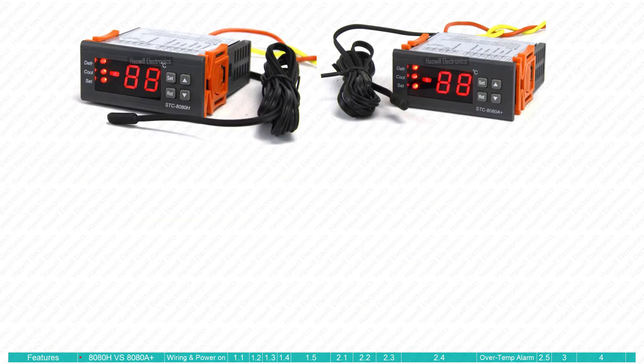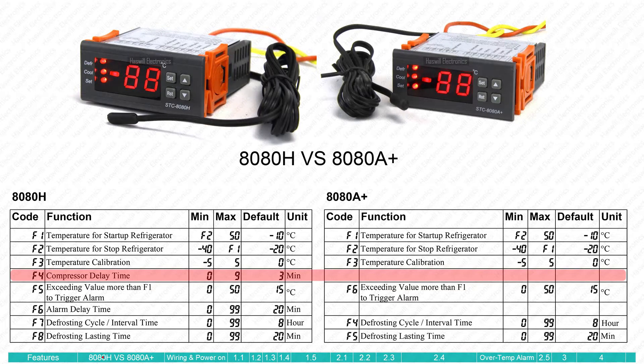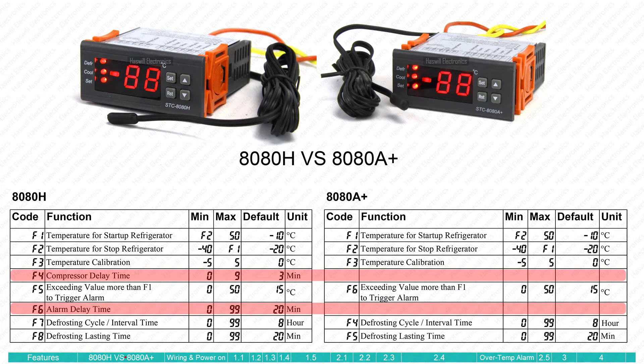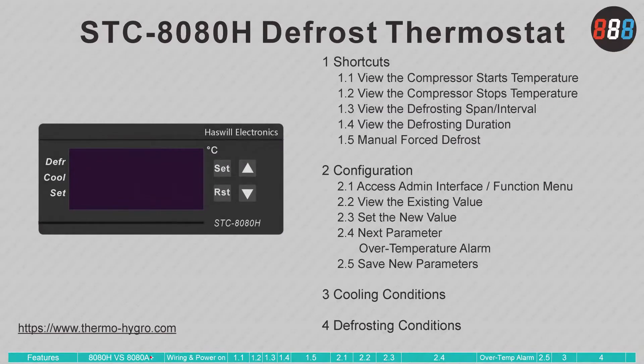The STC-8080H and 8080A Plus are similar, but the 8080H offers two additional options. First, the compressor delay time is editable in the 8080H, unlike the 8080A Plus which has a fixed three-minute delay time. Also, the 8080H allows the user to set an alarm delay time from 0 to 99 minutes, which the 8080A Plus does not have. Therefore, we'll use the 8080H as our example.